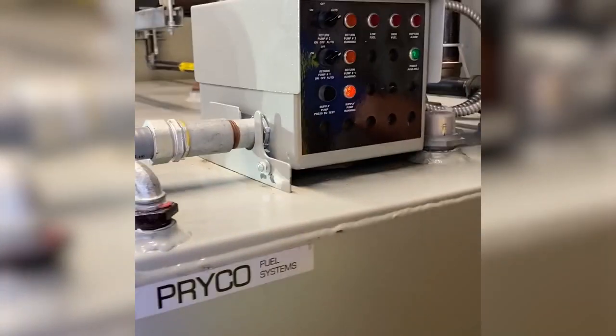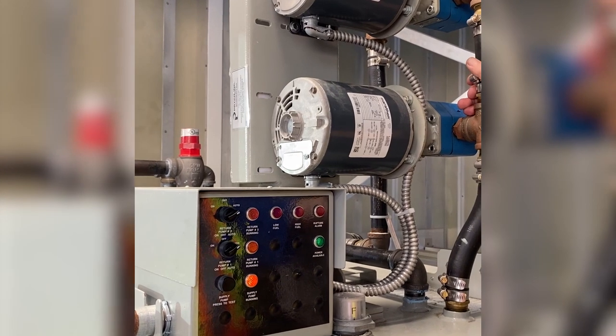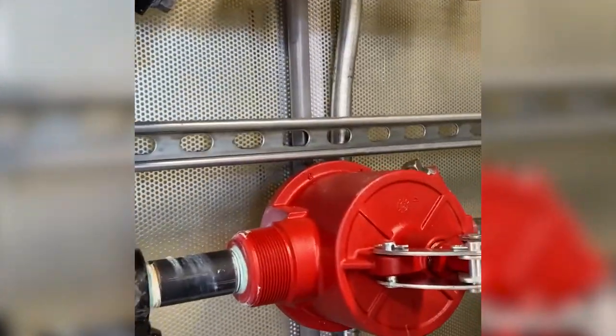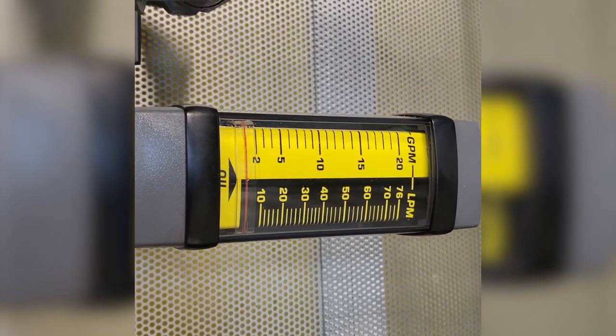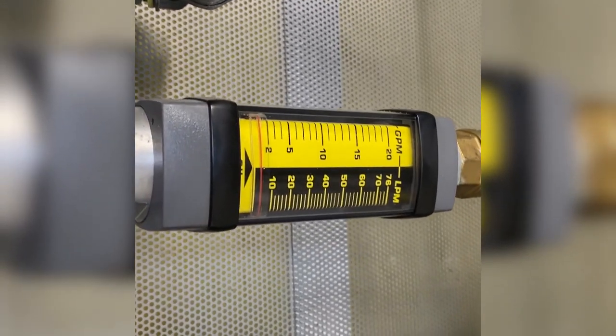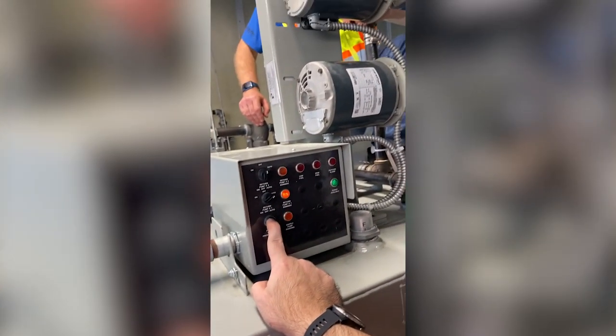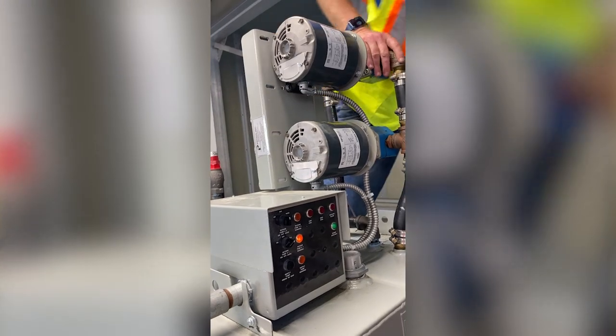This is me doing pump testing at the generator — making sure the fuel systems work, that the supply pumps are filling the day tank, and that when it reaches the high level, the return pumps kick on. I liked this gauge that actually showed whether we were moving fuel or not. That's just one small piece of what we're doing during the whole integrated systems testing.